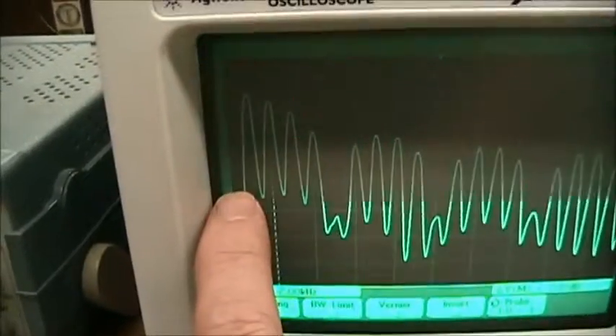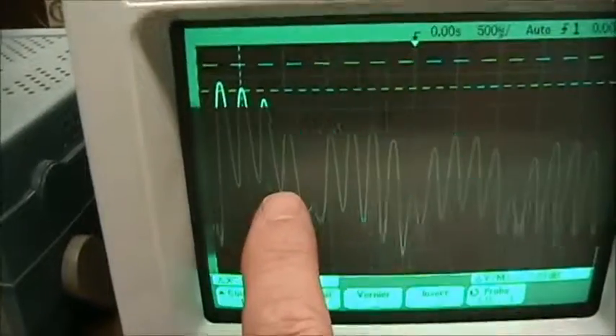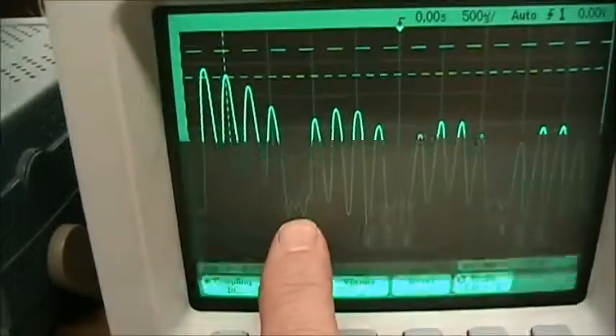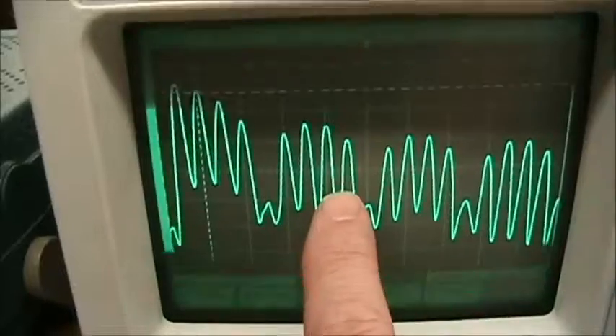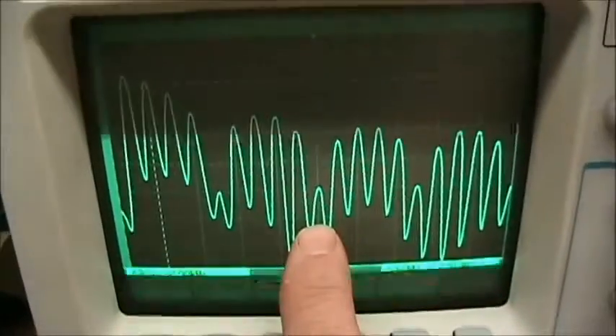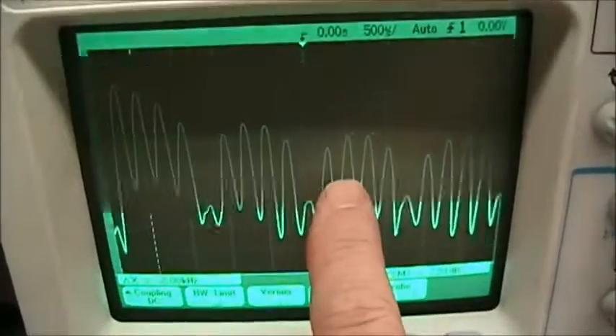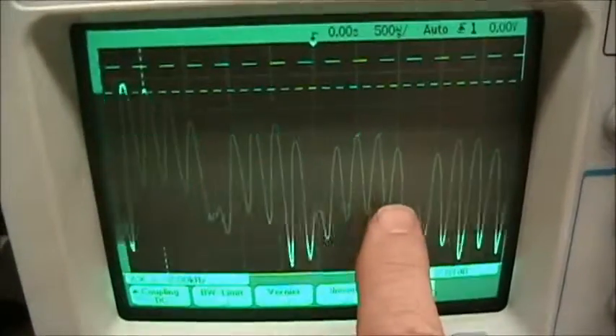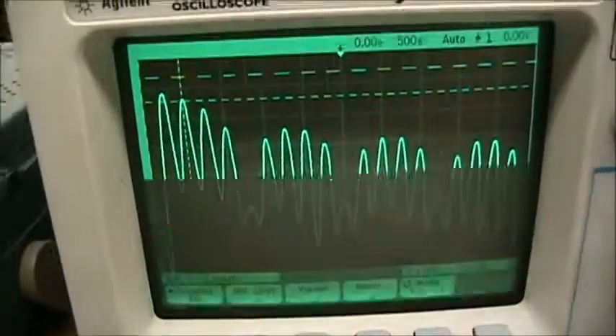So we have fundamental, second, third, fourth — fifth is low — sixth, seventh, eighth, ninth — tenth is low — eleventh, twelfth, thirteenth, fourteenth — fifteenth is low — and on up.